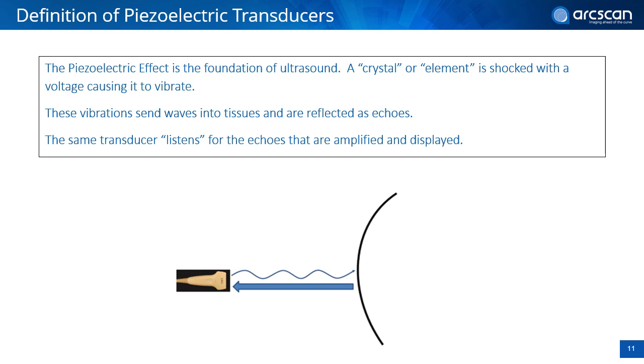Ultrasound is created with a piece called the piezoelectric transducer. This is the foundation of ultrasound. It's a crystal. It gets excited and vibrates with electricity. The piezoelectric has the ability to emit sound and receive the echo being returned from the organ or the tissue that we're examining. So it converts electricity into sound waves, which the instrument then measures. A sound wave or vibration is sent out into tissues, and when a change in density is detected, the sound wave is reflected back as an echo. The same transducer listens for the echoes that are amplified and then displayed.